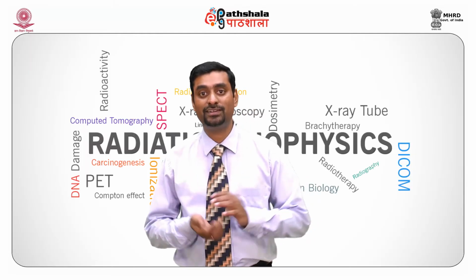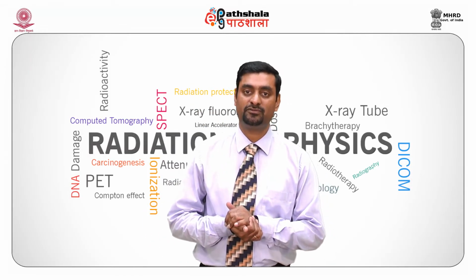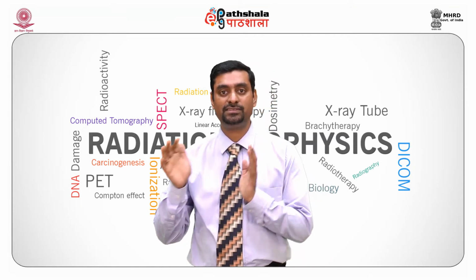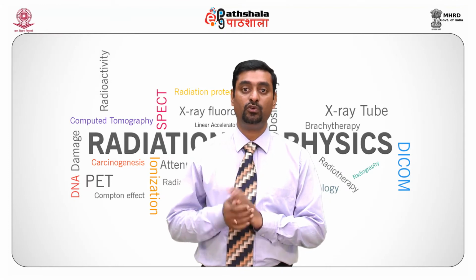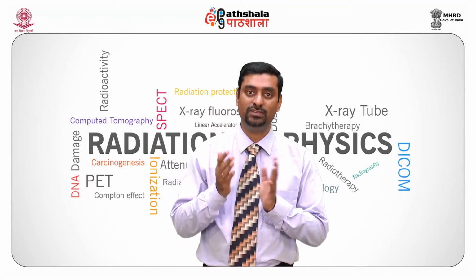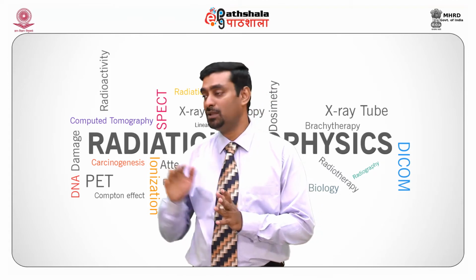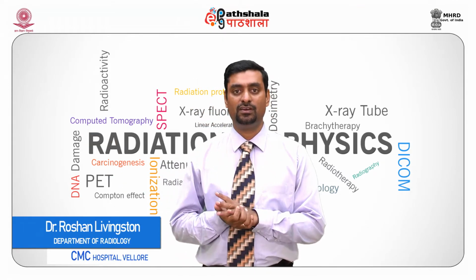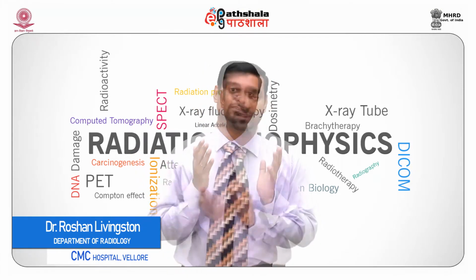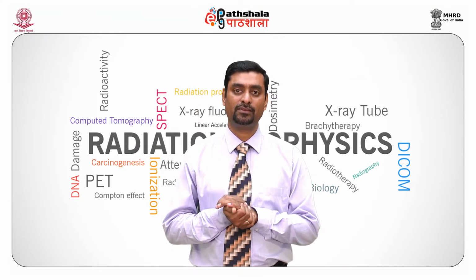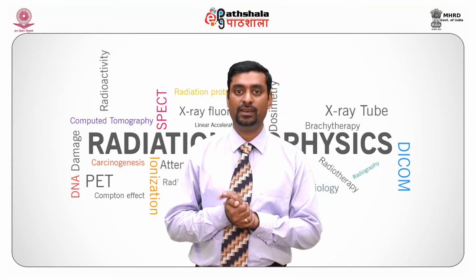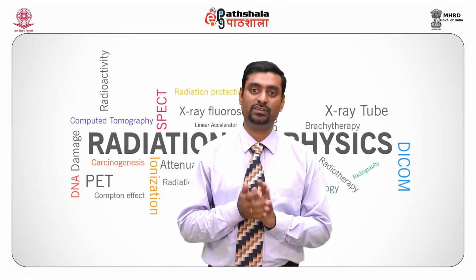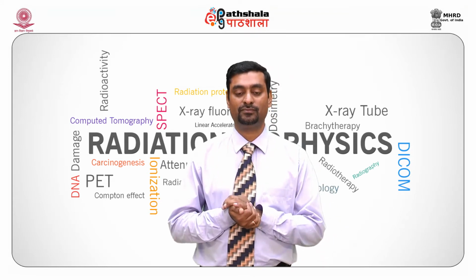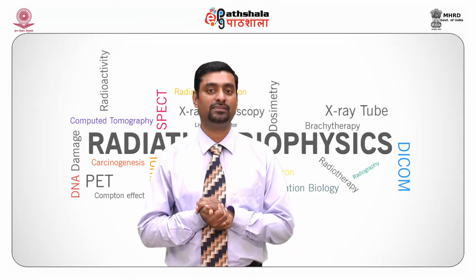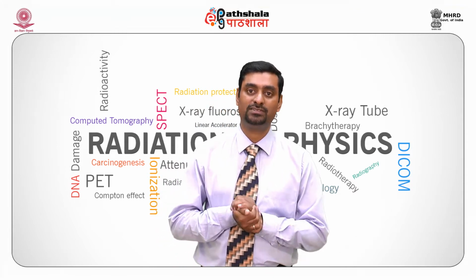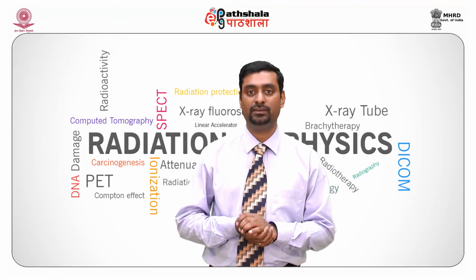The advantages of the CR image phosphor plate or the CR cassette are that the existing X-ray machines can be used. You can replace the film screen combination with these CR cassettes. They can be used for mobile radiography machines, and if a single image plate has artifacts, it can be removed and replaced with a different, newer IP plate. Radiation dose to the patient is reduced if optimized exposure factors are included in the radiographic techniques.